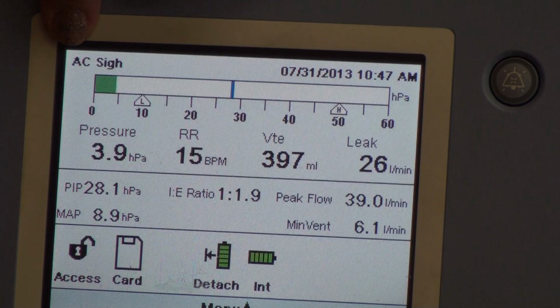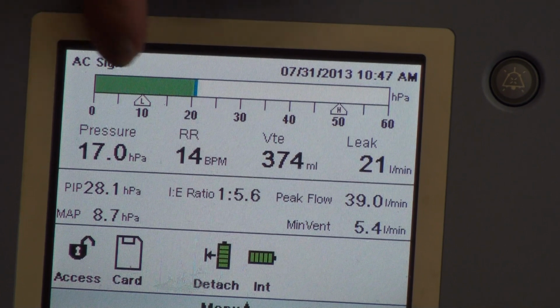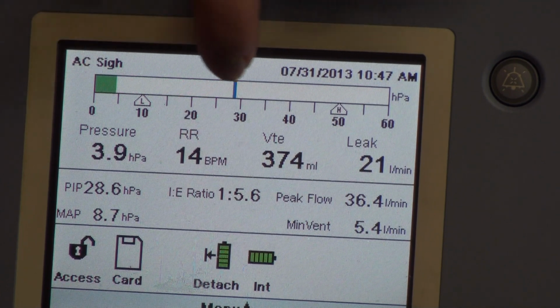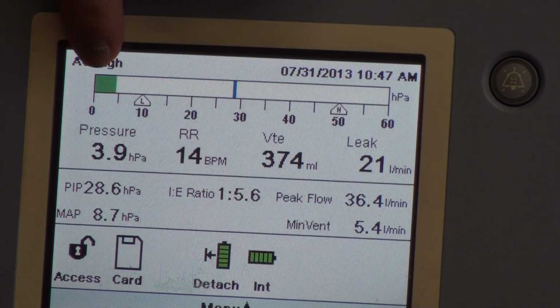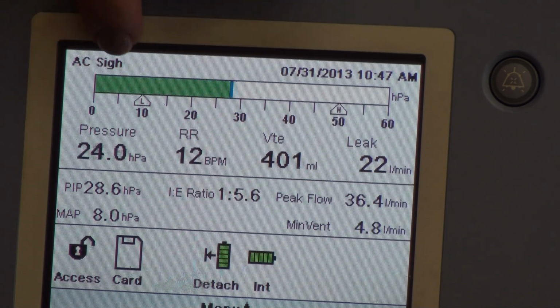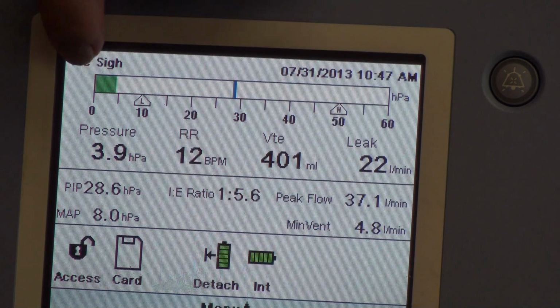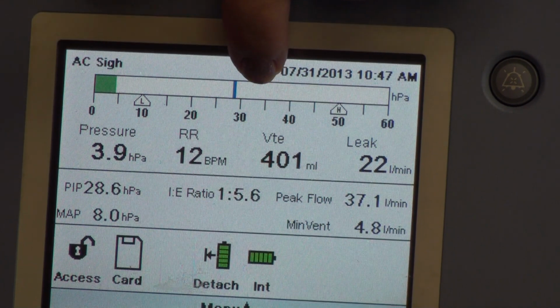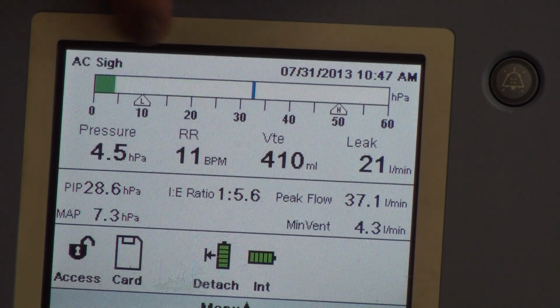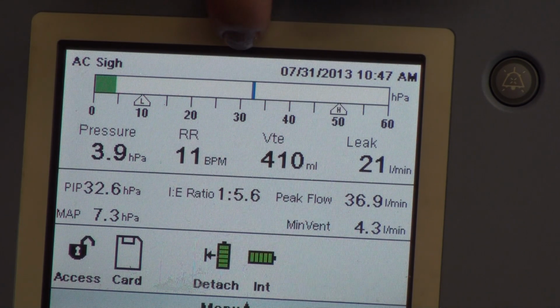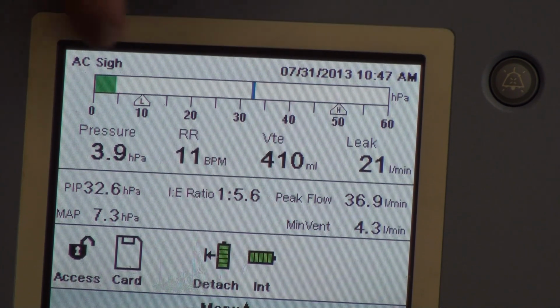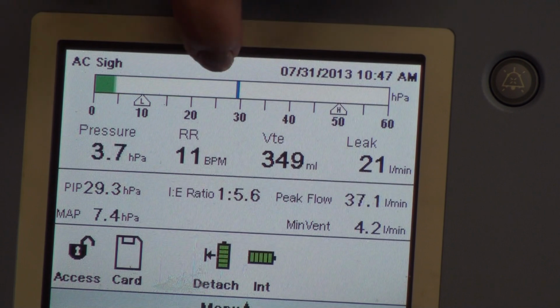E is going to be your airway pressure manometer, and that just displays breath by breath what's going on and what pressure is going on with that breath. So it starts out with your PEEP, and this PEEP looks like it's set at about maybe 4, and then it goes all the way up until it delivers the breath, and then it comes back down, and it leaves a line where that peak inspiratory pressure was at the previous breath. And the next breath comes in, the line disappears, and it leaves it where that one is at.